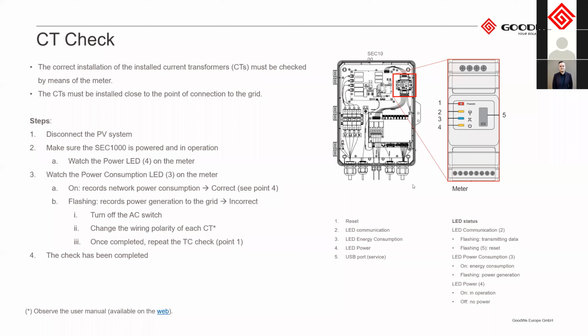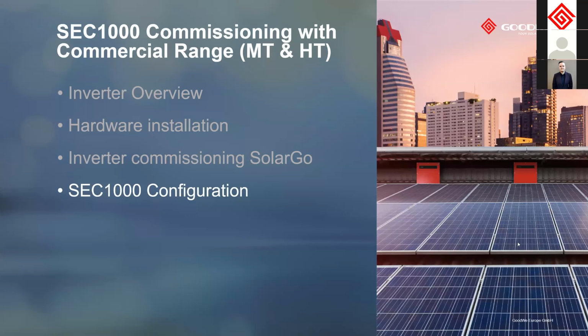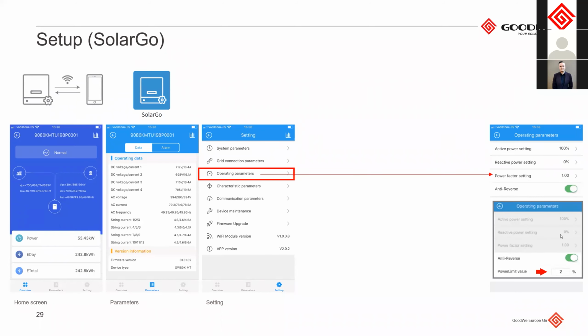So then the last question, is there any requirement of setting an inverter after connecting a GM3000? Yes, as you'll see in the presentation, we have the power limit function, which I skipped over for the SEC. If you're just connecting an SMT with a GM3000 in SolarGo, you set the anti-reverse or power limit, you enable that, and you select your power limit value. If you have an inverter with an LCD, the SMTs do have LCDs as an option, that can also be set on the LCD of the inverter.